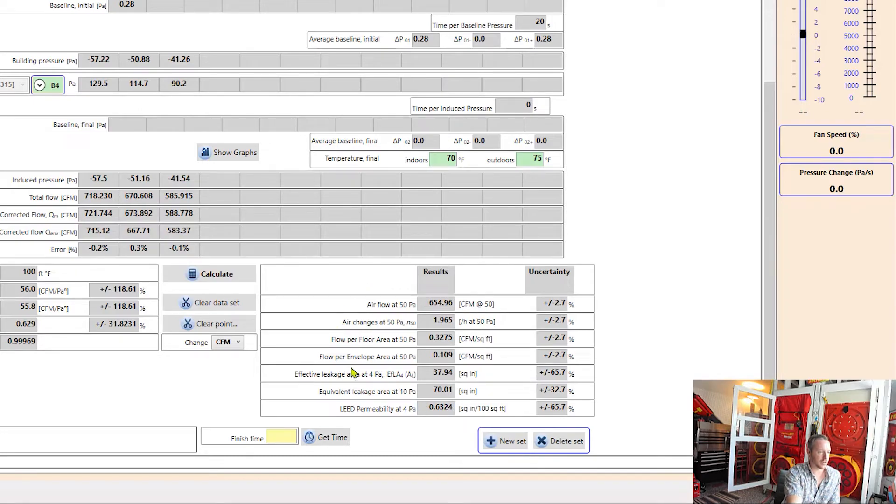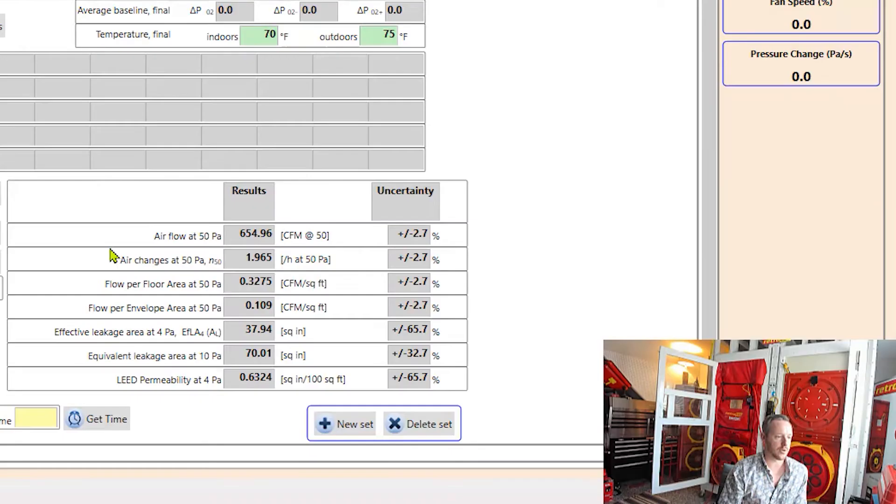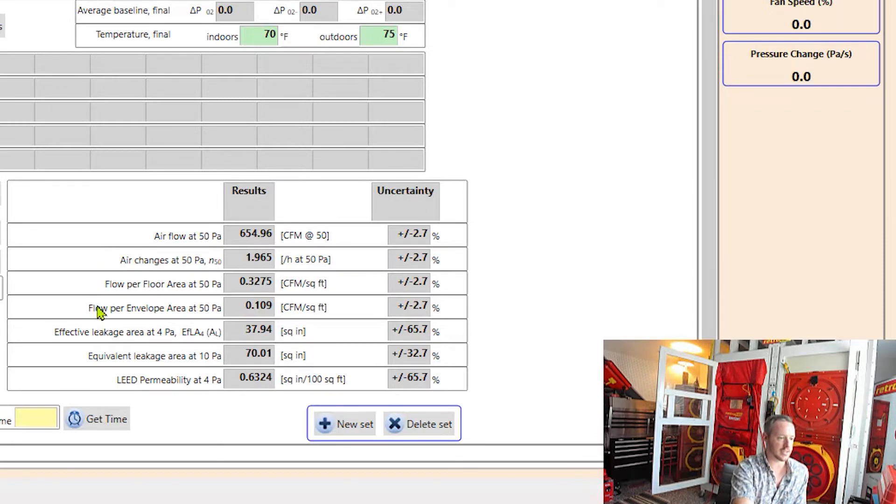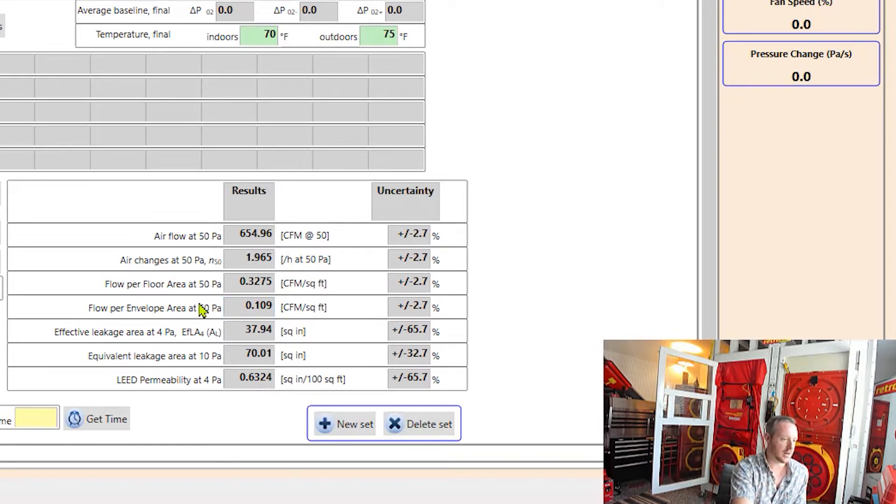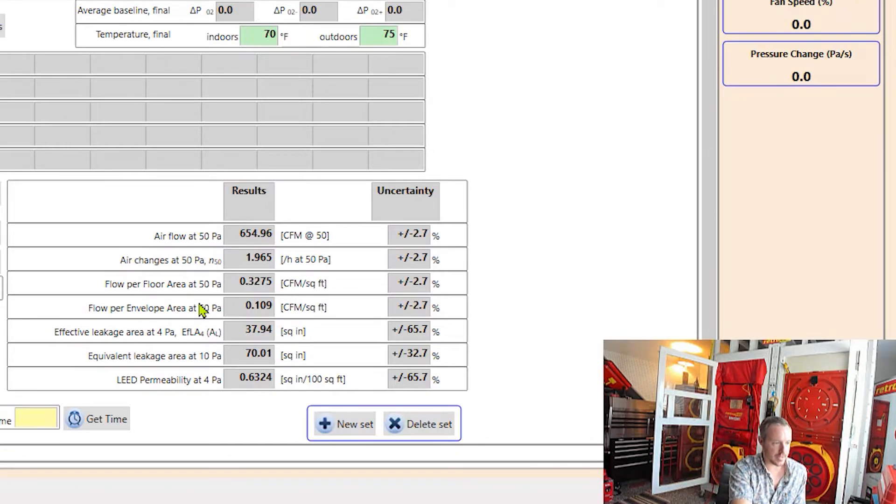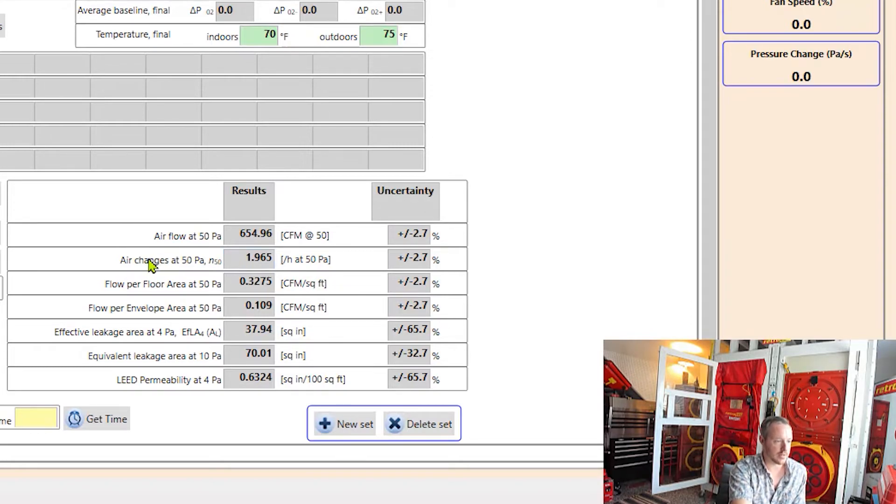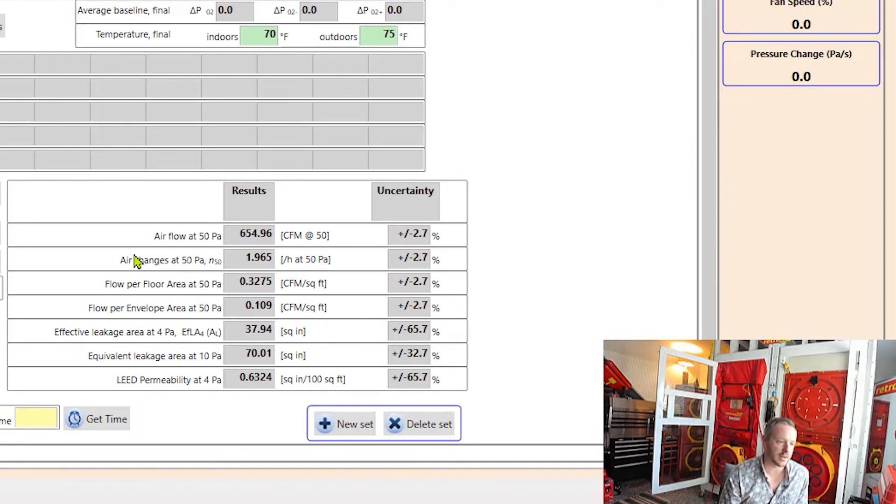So airflow at 50 Pascals was about 655 CFM. And then if I want to look at the flow per envelope area at 50 Pascals, I can see that here the fourth row down. And that's 0.10 CFM per square foot of envelope area. I can also see air changes per hour that's in here also.